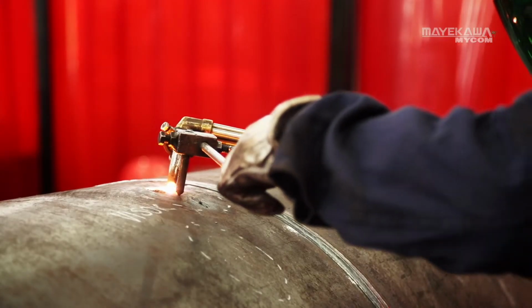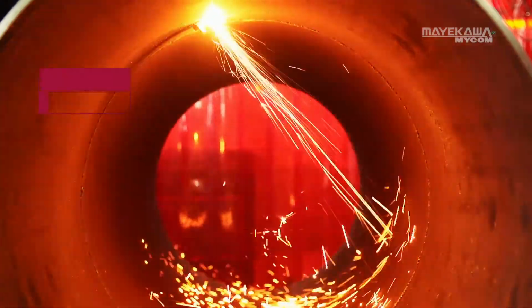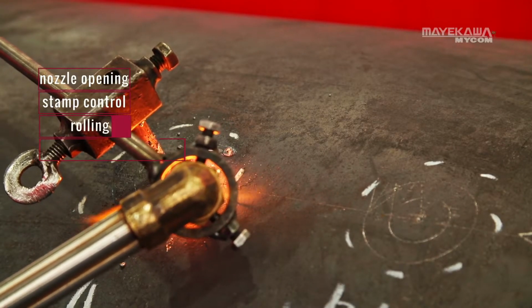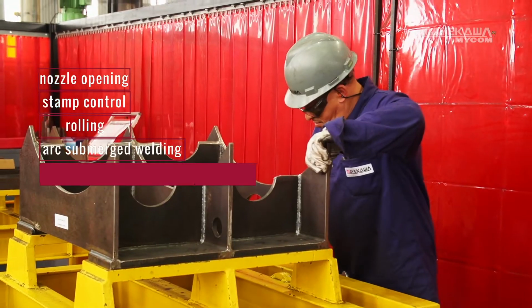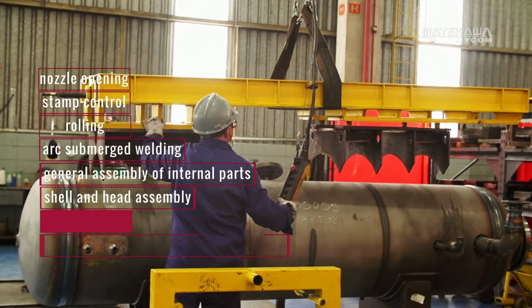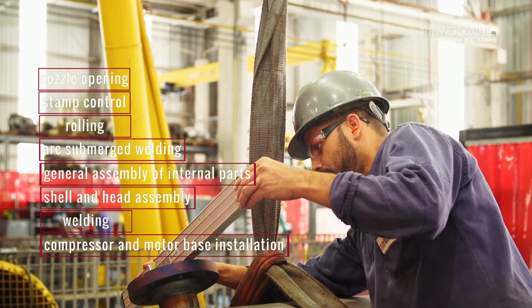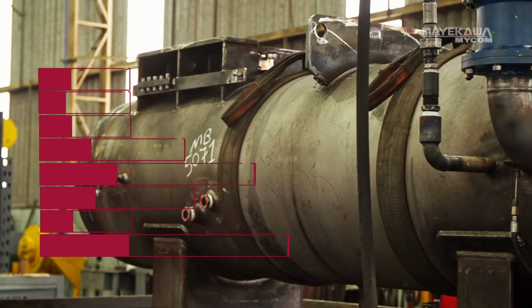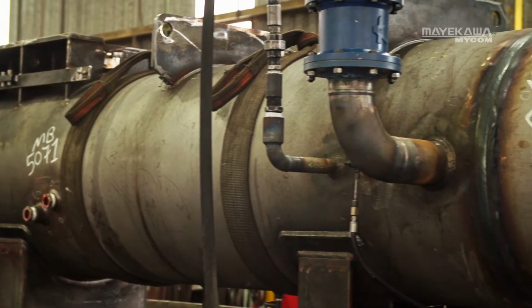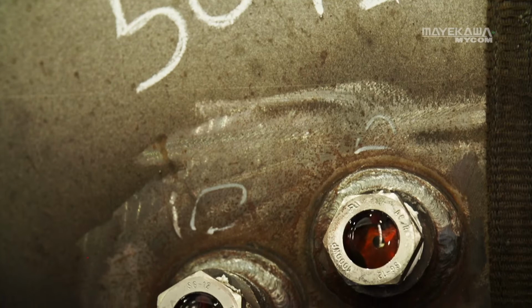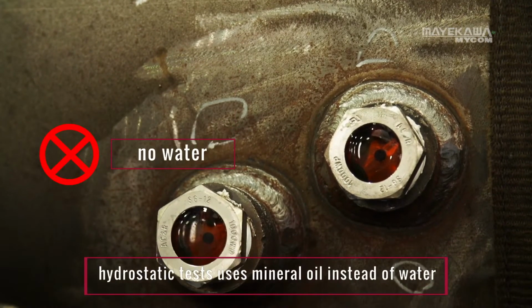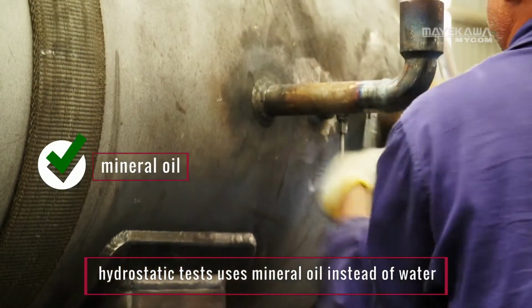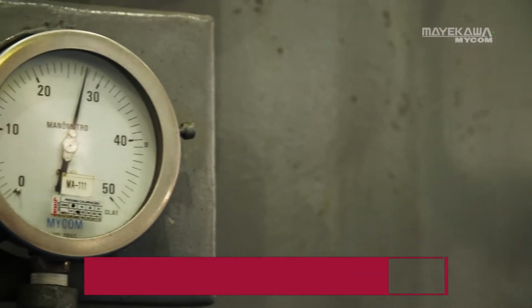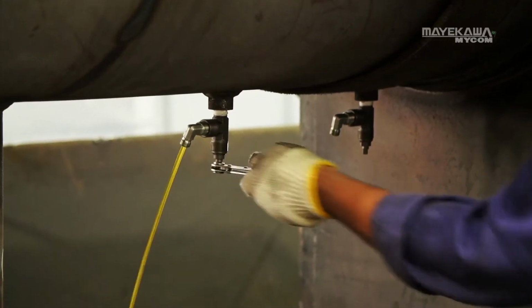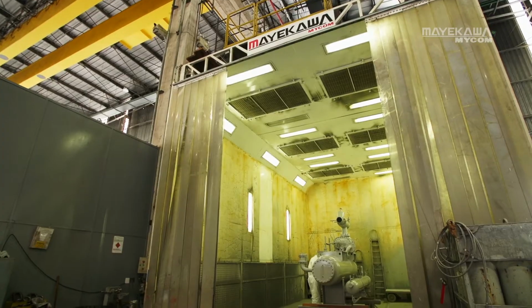After fabrication activities such as general cutting process for nozzle opening, stamp control, rolling, arc submerged welding, general assembly of internal parts, shell and head assembly, welding and compressor motor base installation are made. Hydrostatic test for mechanical strength is carried out. Our hydrostatic tests for pressure vessels use mineral oil instead of water, which creates an internal coating in the pressure vessel and protects against rust and oxidation. After the hydrostatic test is performed, the pressure vessel is sent to primer painting coat.